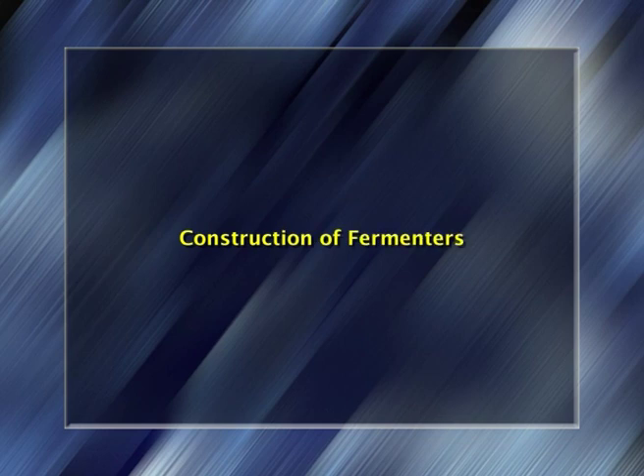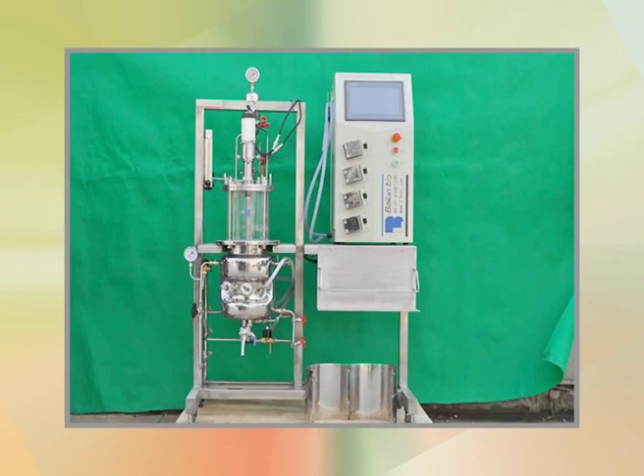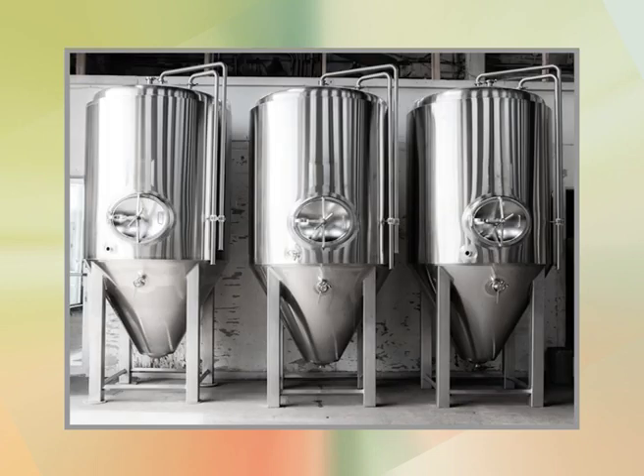Moving on to the second part of our topic, the construction of fermenters. In fermentation with strict aseptic requirements, it is important to select materials that can withstand repeated steam sterilization. Two basic types of fermenters are used. Type 1: a glass vessel with a rounded flat bottom and a top-flanged carrying plate — all vessels of this type have to be sterilized by autoclaving, and the largest practical diameter for a glass fermenter is 60 cm. Type 2: a glass cylinder with stainless steel top and bottom plates — these fermenters may be sterilized in-situ, but 30 cm diameter is the upper size limit to safely withstand working pressures.